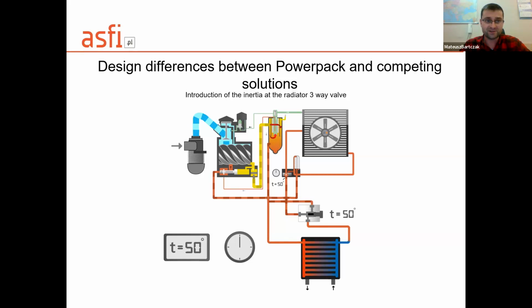Its disadvantage is that without control of the water flow as a function of the oil exchanger outlet, the valve that is responsible for the compressor not overcooling the oil can be responsible for its overheating. What we have on the simulation, I need to give you some input data.